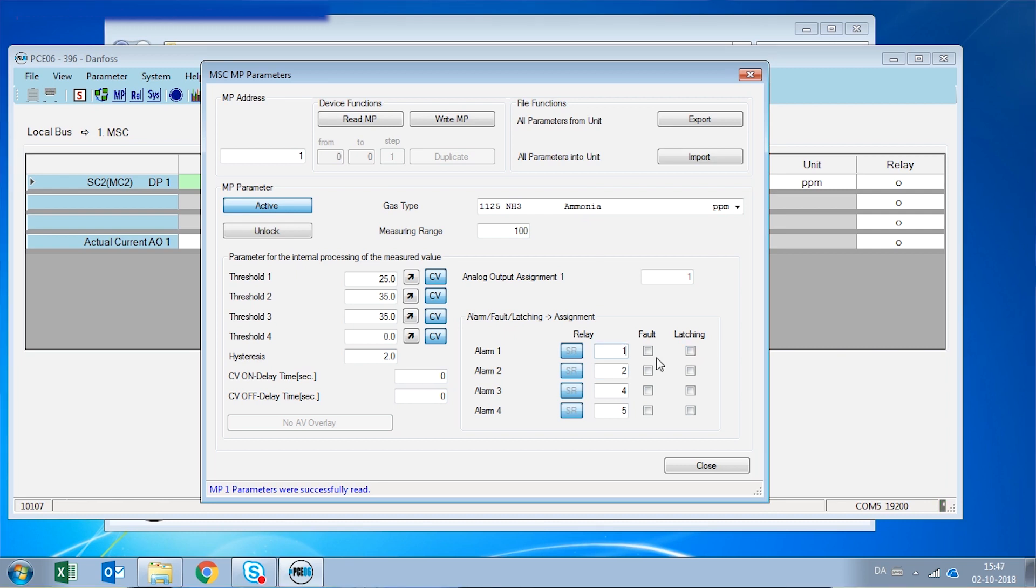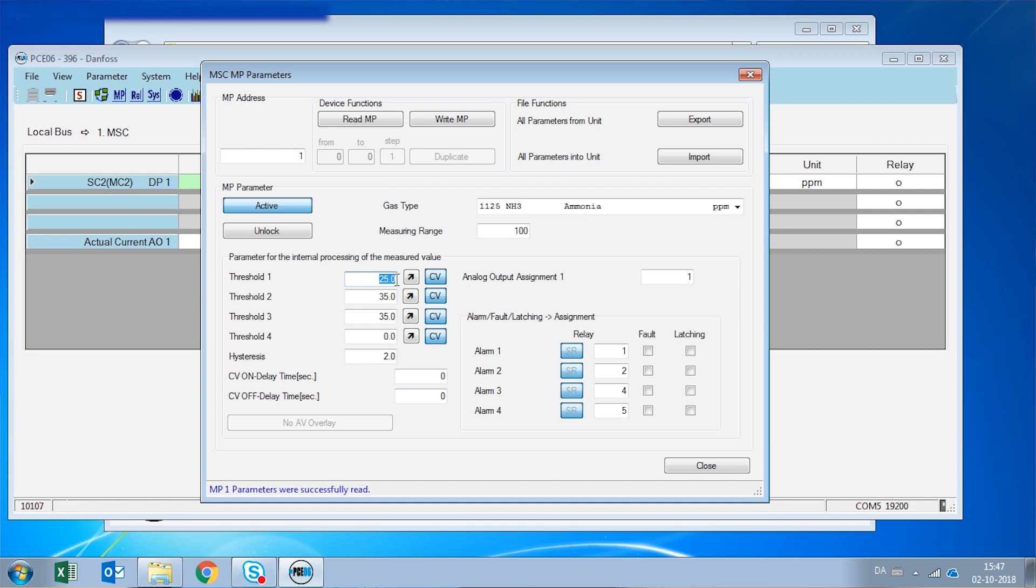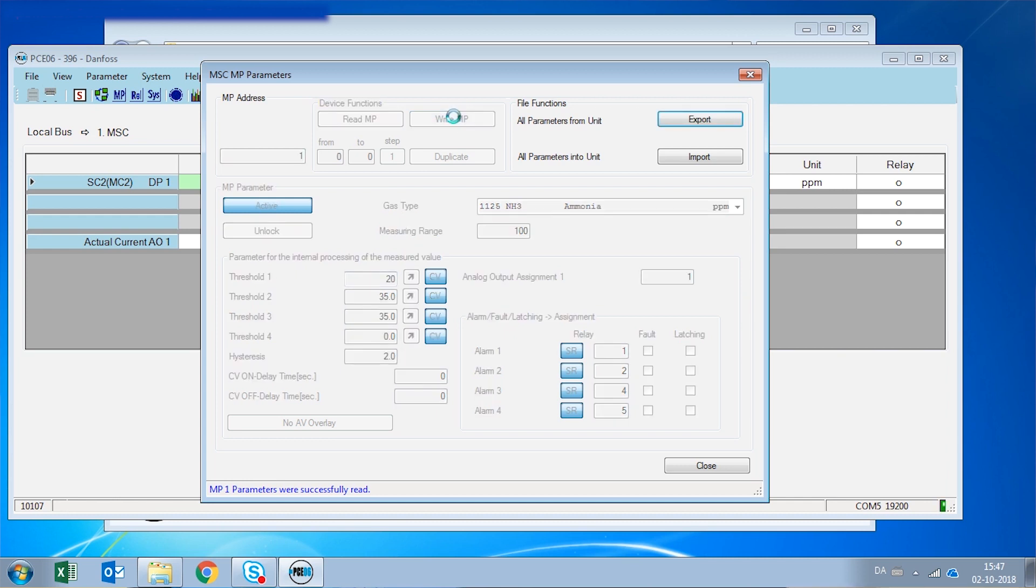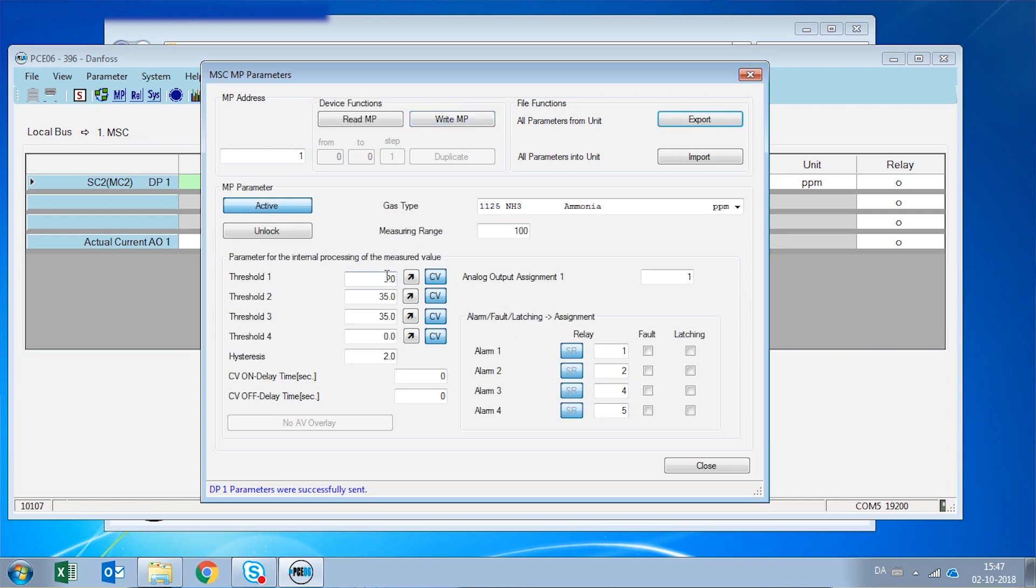If we want to do a change in some of these parameters, for example, if we want to change the threshold from 25 ppm to 20 ppm, all we have to do is enter the new value of the alarm, which in this case will be 20, and then click the button write measuring point. By writing the measuring point we have changed the first threshold from 25 to 20 ppm.